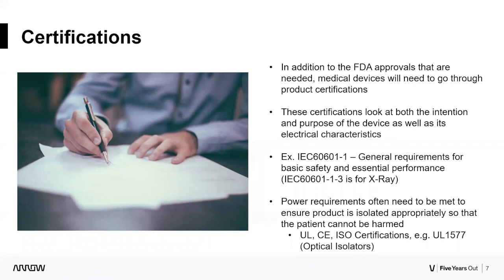An example of this is IEC 60601-1, a general requirement standard for basic safety and essential performance. An example under that is 1-1-3. I'm not joking, this list can go on for hundreds of items for particular devices. The 1-1-3 is particular for x-rays, but that standard talks about particulars for different types of medical devices.